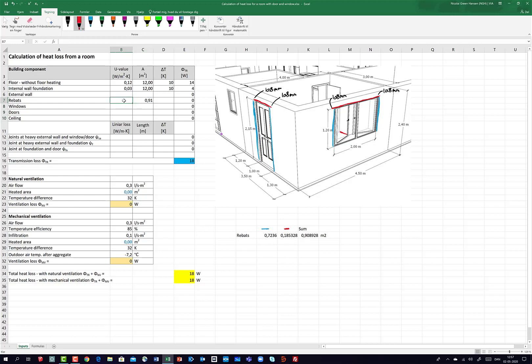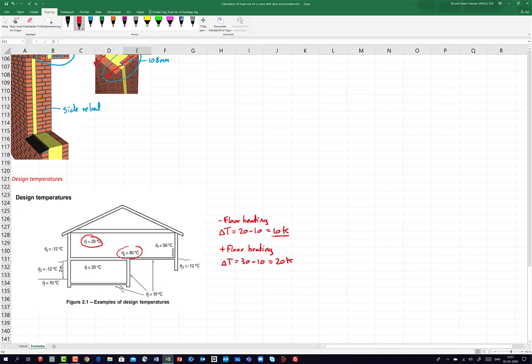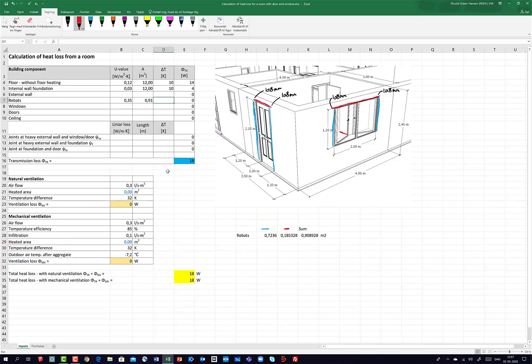I assume a U-value of 0.35 — a fictive value you would calculate yourself. The temperature difference: from the formulas tab under design temperatures, indoor is 20 degrees and outdoor is minus 12 degrees, so the temperature difference is 20 minus (minus 12), which is 32 Kelvin. Using φ = U × A × ΔT gives 10 Watts through the rebates.